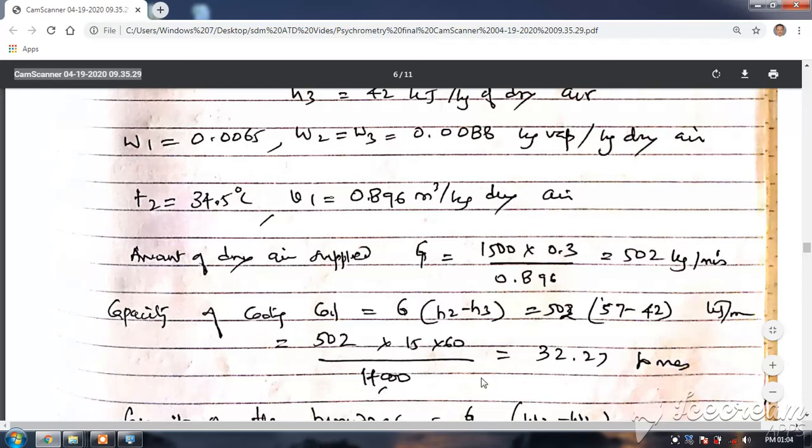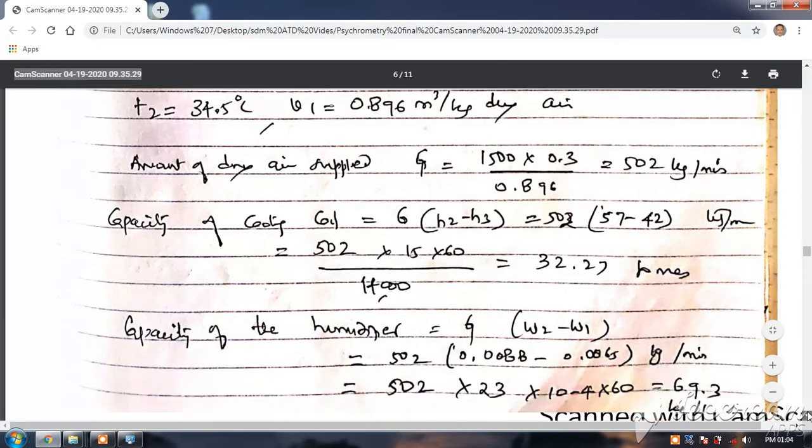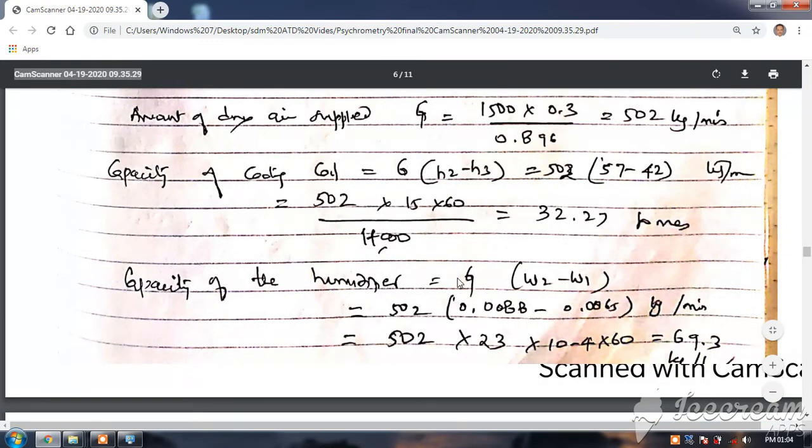Otherwise also you can divide this by 60 and again divide by 3.5, so you will get tons only. And the capacity of humidifier: again this mass of G into omega 2 minus omega 1, so 502 into 0.0088 minus 0.0065, so you will get this as 69.3 kg per hour.